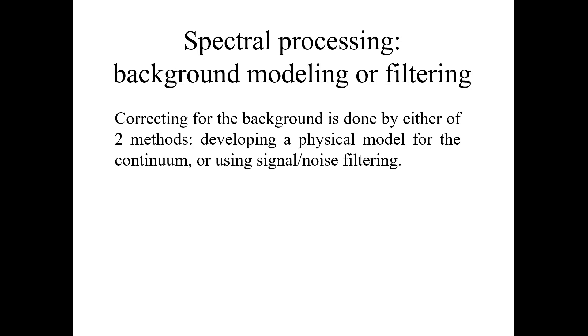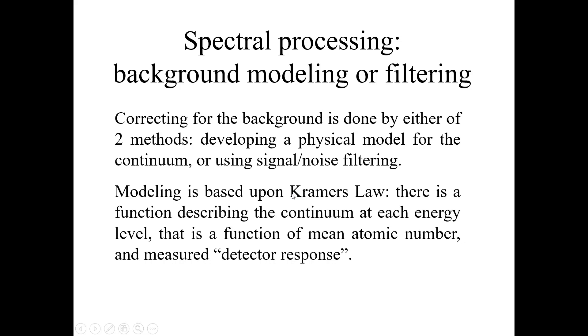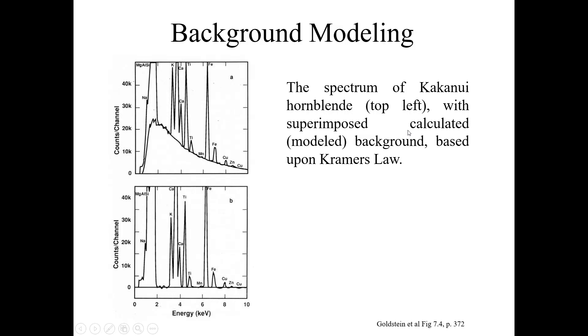The two methods are: developing a physical model for the continuum, or using digital filtering. The modeling approach is based upon Kramers' law, which provides a function describing the continuum at each energy level as a function of mean atomic number and the detector response.